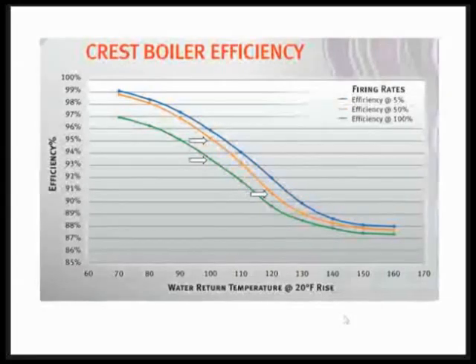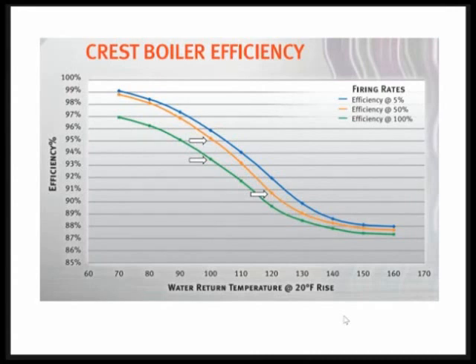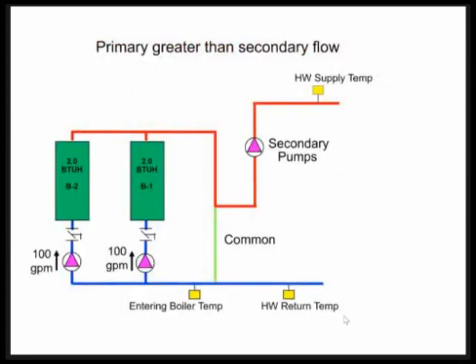So we've actually gone the wrong way. And this is what happens a lot with system efficiency optimization and constant flow primary variable flow secondary. So do we want to do that? Maybe in a water source heat pump job, we might want to consider it when our loop temperatures are very low. But in a job where we've designed around 120, 140, 160 degrees, it might not be the best idea. System efficiency optimization in theory works great. In practice, maybe not so well.